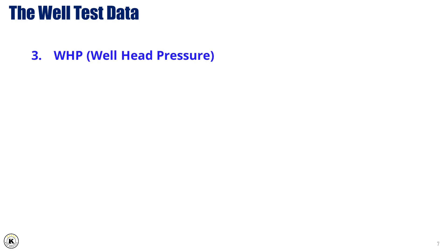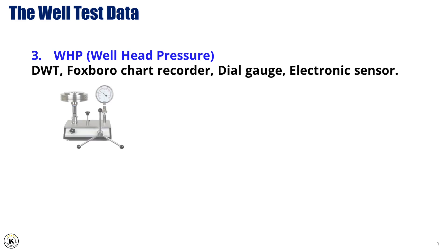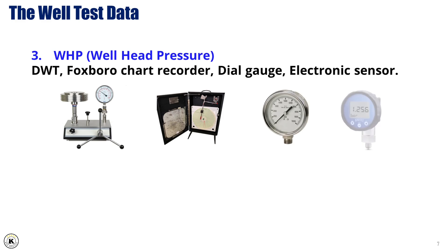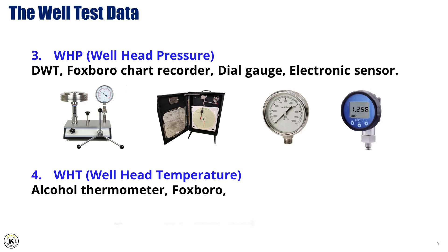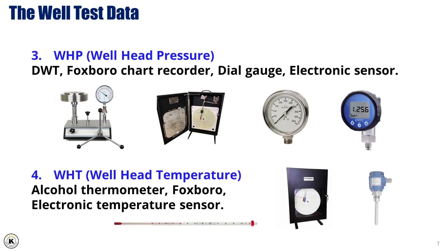3. Wellhead Pressure — to measure the wellhead pressure, tools such as the deadweight tester, Foxboro chart recorder, dial gauge, or electronic sensors are commonly used. These instruments help monitor and record the pressure at the wellhead, ensuring it is within safe operating limits. 4. Wellhead Temperature — typically measured using an alcohol thermometer, Foxboro instruments, or electronic temperature sensors, which monitor the temperature at the wellhead and help identify issues related to temperature fluctuations during testing.